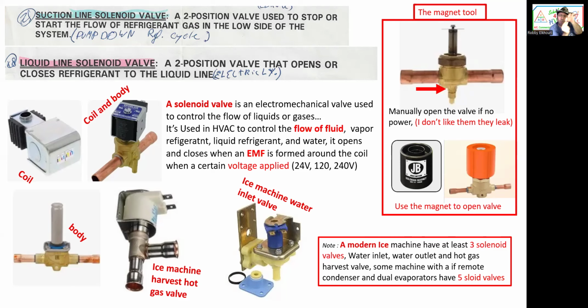We also have some valves with a manual stem at the bottom, so you can manually open it. They leak Freon. I never installed it. I don't like them. They should not even exist. Pretty stupid. If there is no power and you have to recover or do something, the only thing you're going to do is pretty much remove the refrigerant. And you can't do it if this valve is closed. So you use a little magnet, you put it in, boom, it will open the valve. All right. The magnet to open the valve is a lot easier than to unscrew the screw, a pain in the butt, and they leak Freon.